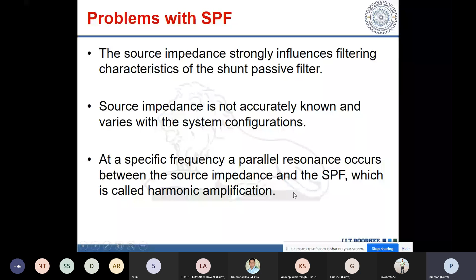So what is the other possible way of eliminating the harmonics? The power electronic controller solutions are the shunt active filter, the series active filter, and the unified power quality conditioner. Shunt active filter is just like a shunt passive filter. It provides ideally low impedance for that harmonic component, or you can say it acts as a current source and injects the harmonic component required by the load, so that the harmonics are not drawn from the supply but are provided by the shunt active power filter.